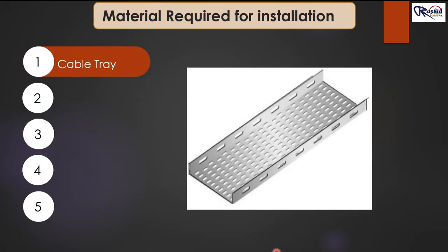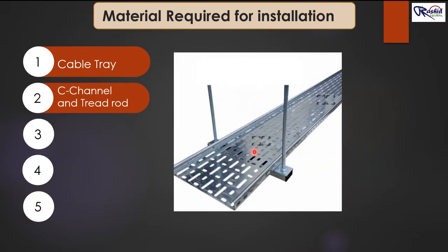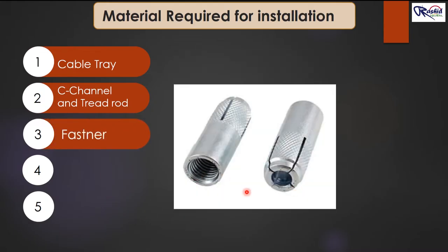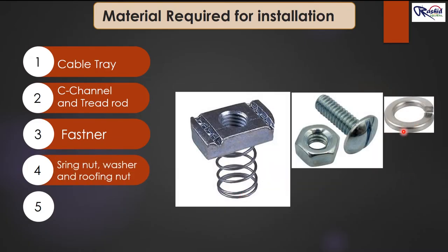Here we need: first, perforated cable tray; second, C-channel and thread rod, which is used to hang the cable tray; third, fasteners, which are used to fix the thread rod in the ceiling. There are different sizes of fasteners available in the market — we will choose the one compatible with the thread rod.